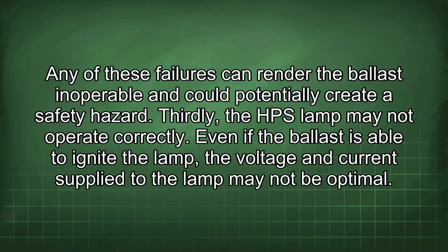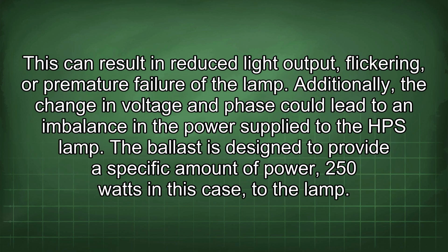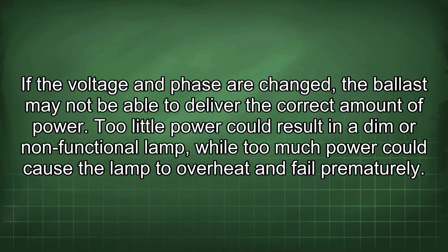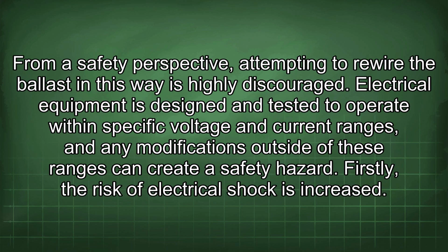Thirdly, the HPS lamp may not operate correctly. Even if the ballast is able to ignite the lamp, the voltage and current supplied to the lamp may not be optimal. This can result in reduced light output, flickering, or premature failure of the lamp. Additionally, the change in voltage and phase could lead to an imbalance in the power supply to the HPS lamp. The ballast is designed to provide a specific amount of power, 250 watts in this case, to the lamp. If the voltage and phase are changed, the ballast may not be able to deliver the correct amount of power. Too little power could result in a dim or non-functional lamp, while too much power could cause the lamp to overheat and fail prematurely. From a safety perspective, attempting to rewire the ballast in this way is highly discouraged.